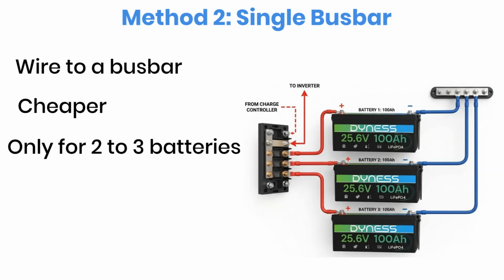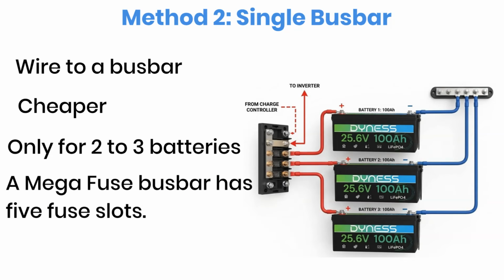For a system with only 2 or 3 batteries, it's difficult to beat this option in terms of value. The downside is expansion. A typical mega fuse busbar has 5 fuse positions. One position is commonly used for the inverter, another for the charge controller, leaving only 3 positions available for batteries. If you later decide to add another battery or another device, such as a battery charger, DC power supply, or another high-current load, you'll probably need to install an additional fuse block or redesign part of the system.